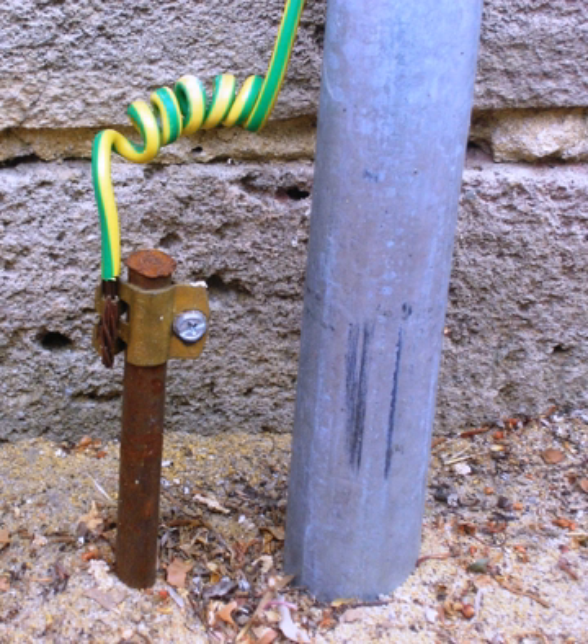Because high-frequency signals can flow to Earth due to capacitive effects, capacitance to ground is an important factor in effectiveness of signal grounds. Because of this, a complex system of buried rods and wires can be effective. An ideal signal ground maintains a fixed potential, zero, regardless of how much electric current flows into ground or out of ground.